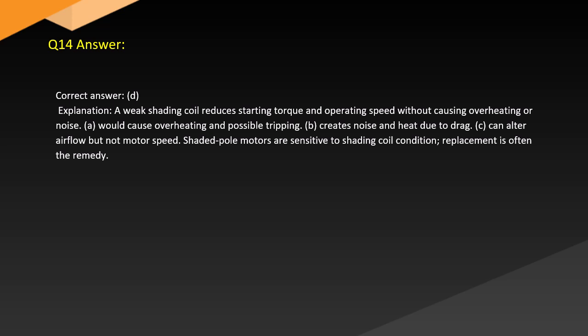Answer. Correct answer: D. Explanation. A weak shading coil reduces starting torque and operating speed without causing overheating or noise. A. Would cause overheating and possible tripping. B. Creates noise and heat due to drag. C. Can alter airflow but not motor speed. Shaded pole motors are sensitive to shading coil condition. Replacement is often the remedy.